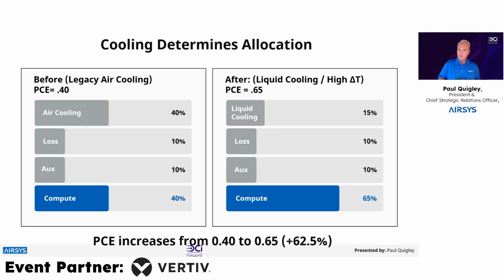So when we were looking at PUE, the lower your PUE number, the more efficient the data center is considered. PCE works the opposite. A 1.0 would equal 100% effective use of power provisioned to the facility, to power provisioned to compute. Currently, we don't have any way of achieving a 1.0, but the closer we get to that 1.0, the more effective we are at finding existing power rather than chasing future power.